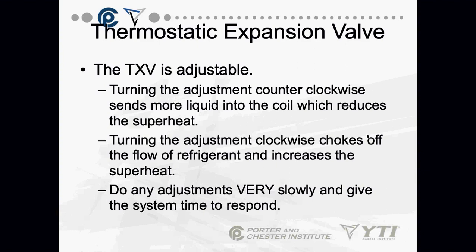I showed you that on the diagram. The more liquid in that coil, the superheat is reduced. Turning the adjustment clockwise chokes off the flow of refrigerant and increases the superheat, because again, less refrigerant, greater superheat.